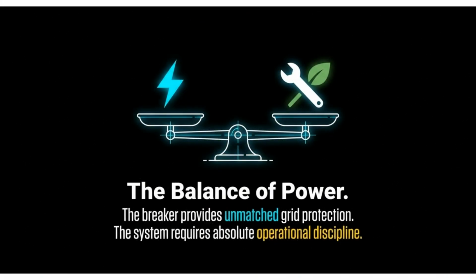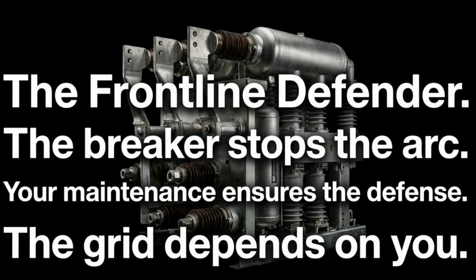This is the balance of power. The breaker provides unmatched grid protection, but the system requires absolute operational discipline. The SF6 breaker is the frontline defender that stops the arc. Your diligent maintenance ensures this defense. Remember, the grid depends on you.